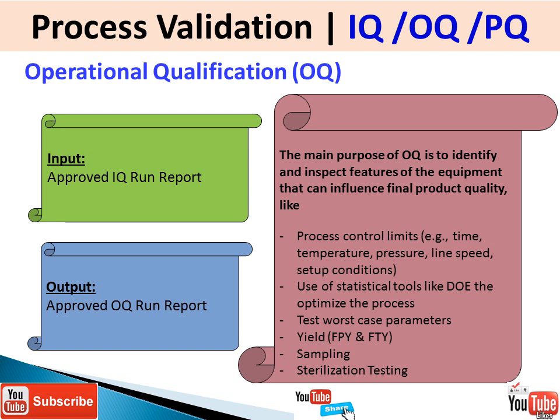The input for operation qualification is the approved IQ report, and the output is the OQ report. During the OQ stage, we inspect process control limits such as temperature, pressure, line speed, and setup conditions. Statistical tools like DOE — design of experiment — are used to optimize the process. We also test worst-case parameters, look at the desired yield such as first pass yield or first time yield, and review sampling plans and sterilization testing requirements.